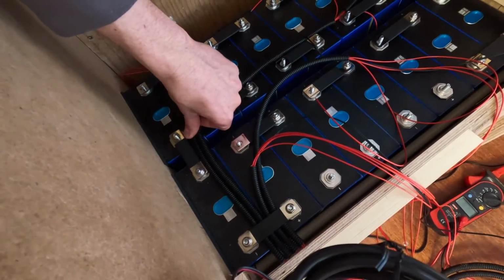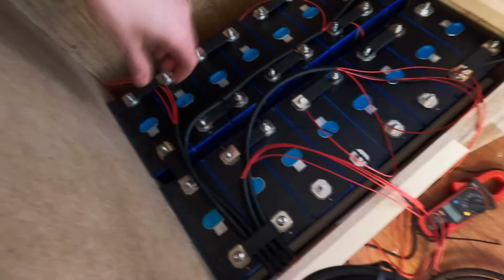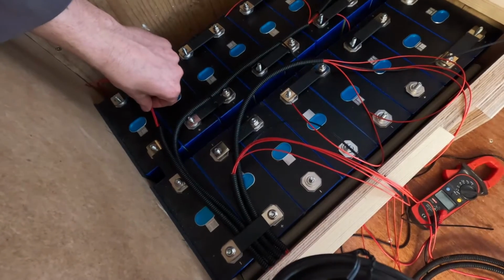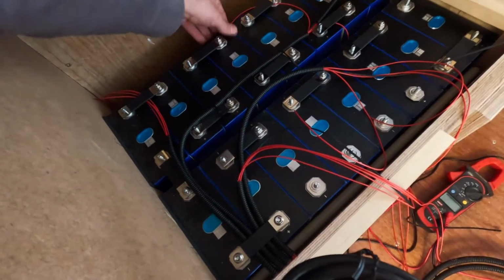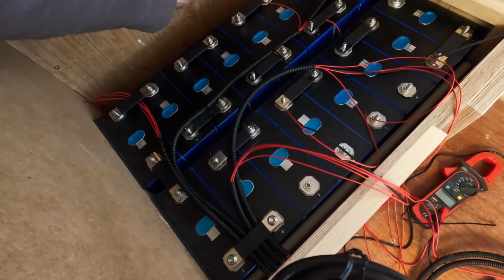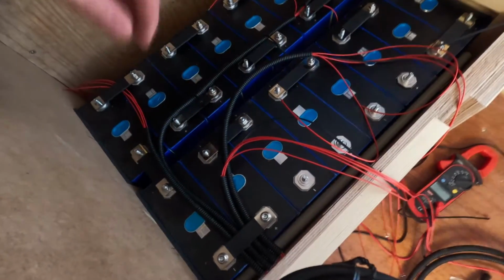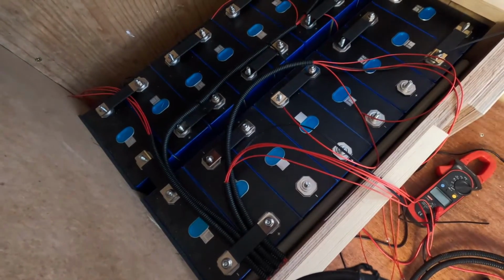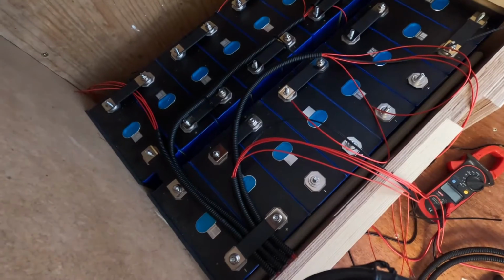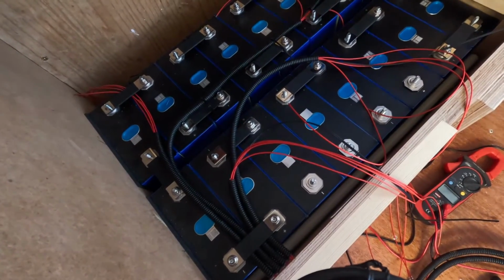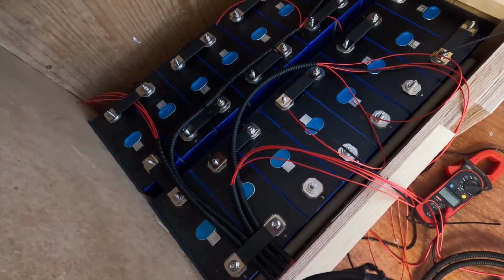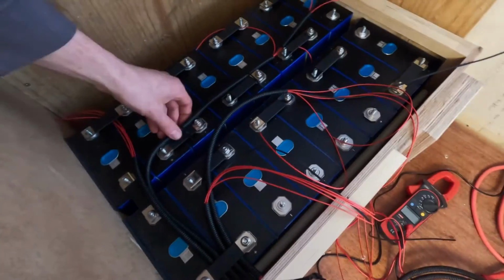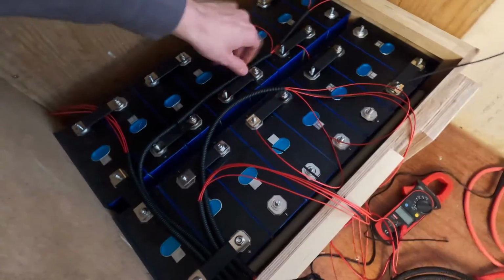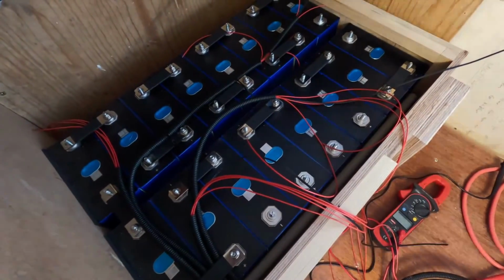I think I will route them in this plastic tubing to protect them, as I won't go with any fuses for these wires. In a short circuit event, these guys will basically self-fuse, they will just burn up. The idea with the tubing is to protect them as well as possible. I really believe in making a good installation from the start. I think that's the best way to protect yourself from any potential hazards or failures in the future. And obviously these guys will not be strapped to the bus bars, that's just for now to measure everything up.